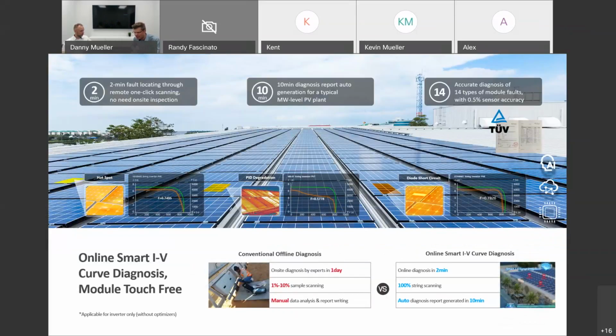The main message is that every Huawei inverter, with its string level monitoring and string current monitoring as well, has the capability with the MPP tracker to scan the whole input voltage range of the inverter to give you the measurement of the IV curve of every single string. And that can be done completely remotely without disconnecting any string of the system at all. The scan typically takes about 2 minutes, and the inverter will power down in those 2 minutes and will then ramp up its power to go through that IV curve.